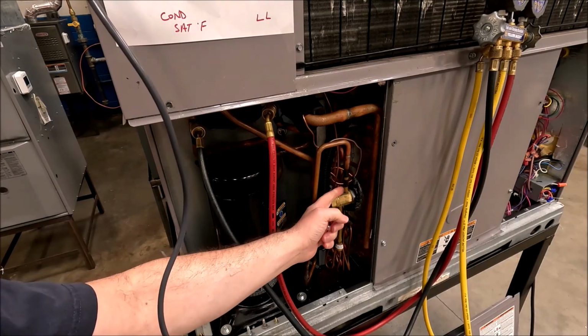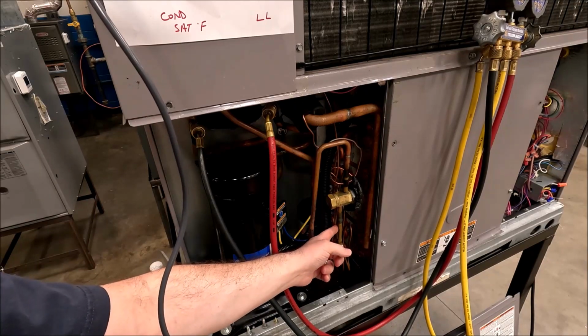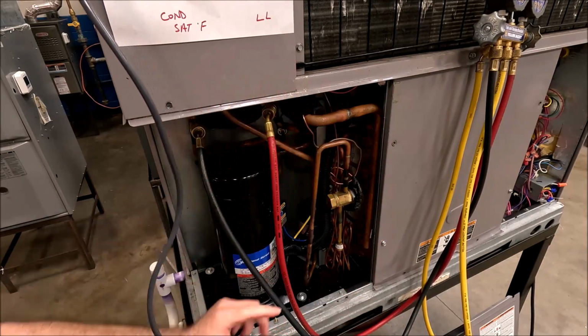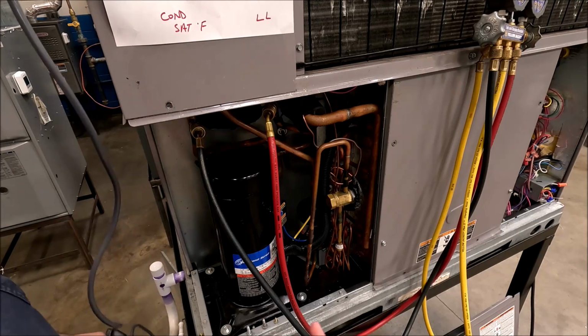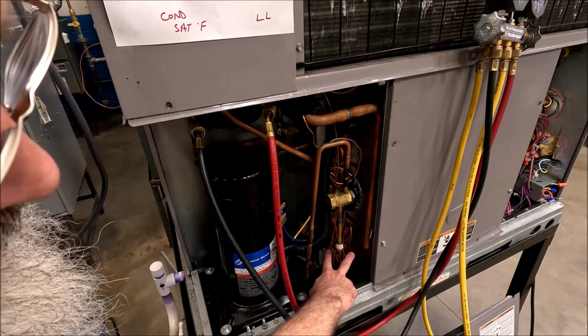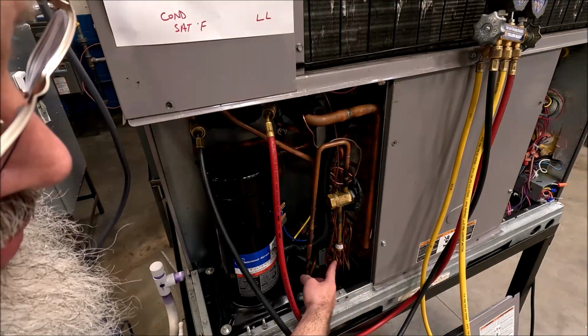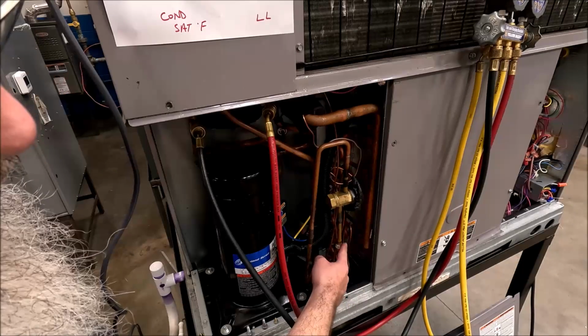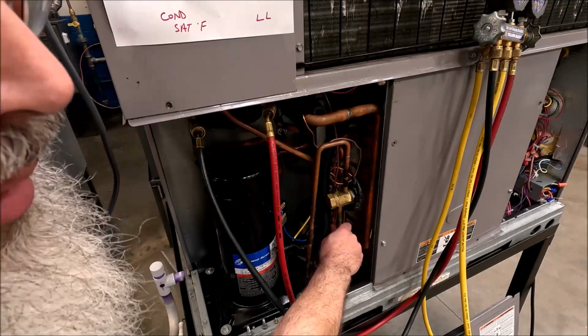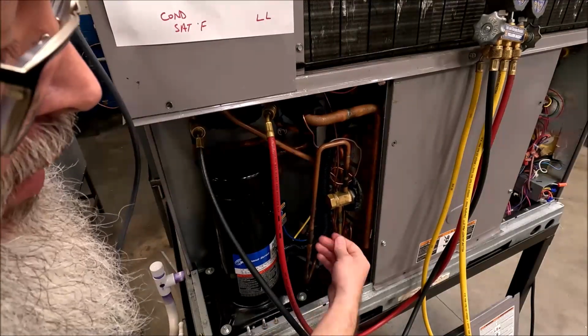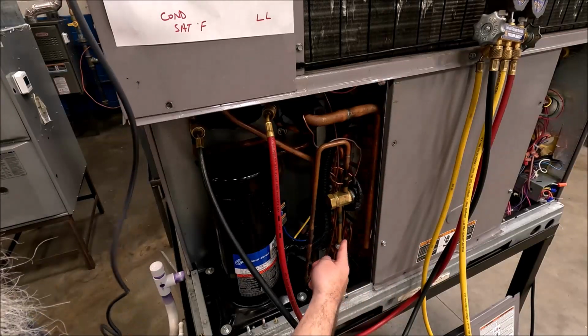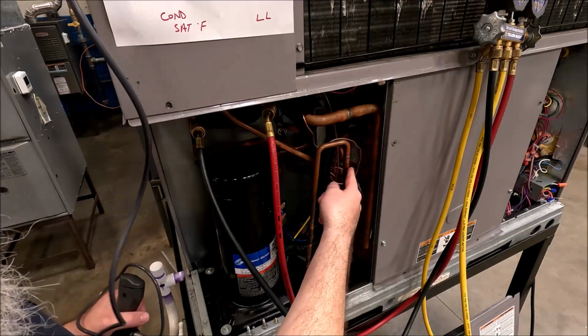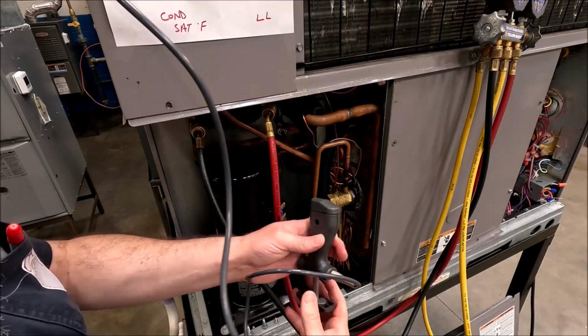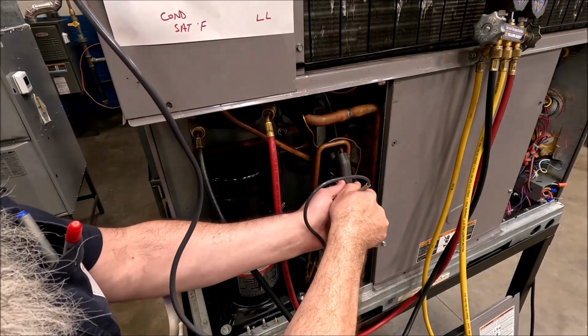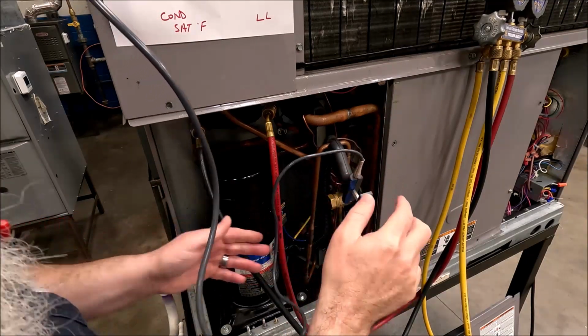So I've got a 3/8 line coming in, and I pretty much have a 3/8 line coming out. You get lost in all the panels and the turns and the twists, but it's fairly easy. One side, you'll see it kind of has these distribution tubes from that distributor. That's going to be your evaporator side. That's going to be cold and probably a little clammy feeling, a little wet, you know, condensation on the line, and we have that here. The other side is just going to be a warm liquid line. This is the line where you can put your pipe clamp on there to get your subcooling.